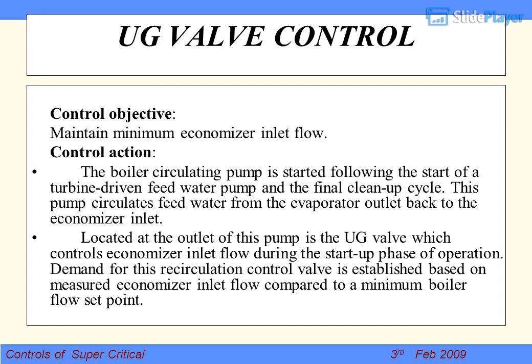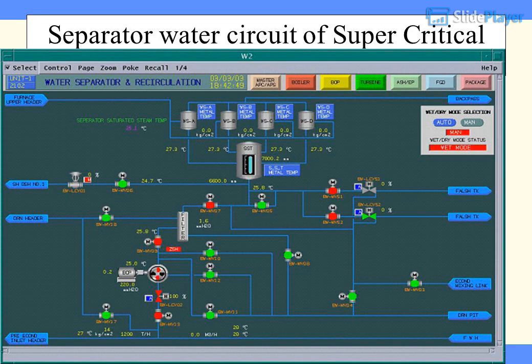UG Valve Control — Control Objective: maintain minimum economizer inlet flow. The boiler circulating pump (BCP) is started following the start of a turbine-driven feed water pump and the final clean-up cycle. This pump circulates feed water from the evaporator outlet back to the economizer inlet. The UG valve, located at the outlet of this pump, controls economizer inlet flow during the start-up phase. Demand for this recirculation control valve is established based on measured economizer inlet flow compared to a minimum boiler flow set point. BCP is required at load less than 30% of TMCR — that is, wet mode.